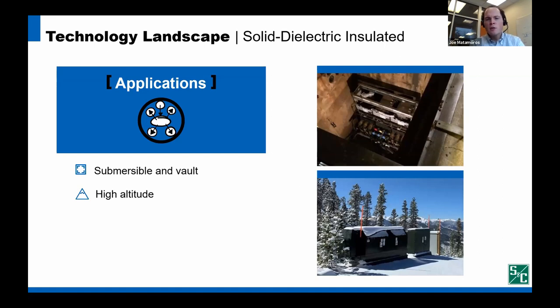SD is also well suited for high altitude applications, like this photo at right. This is from a ski resort. In high altitude SF6 gas insulated gear, the gauge pressure will increase with altitude, and depending on the altitude, that could require a high temperature derating.